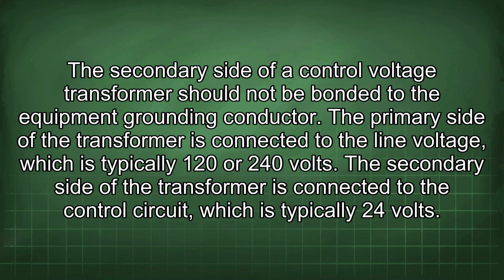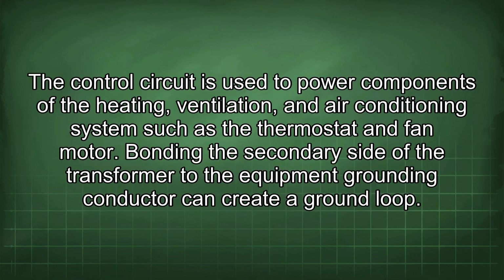The secondary side of a control voltage transformer should not be bonded to the equipment grounding conductor. The primary side of the transformer is connected to the line voltage, which is typically 120 or 240 volts. The secondary side of the transformer is connected to the control circuit, which is typically 24 volts.